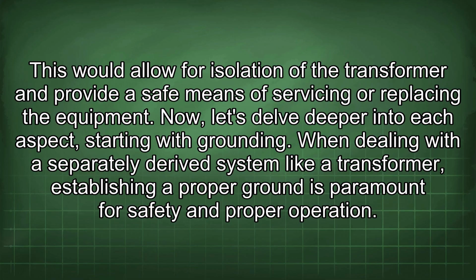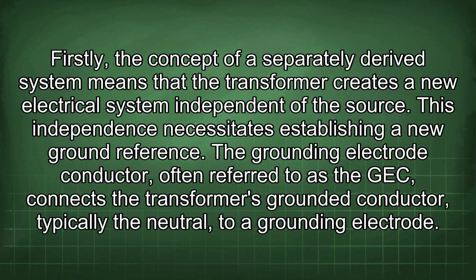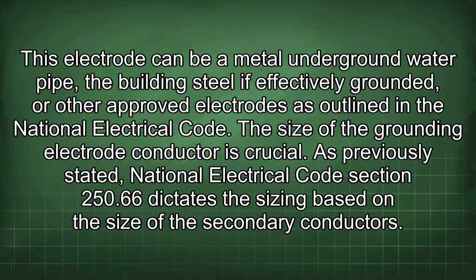Now let's delve deeper into each aspect, starting with grounding. When dealing with a separately derived system like a transformer, establishing a proper ground is paramount for safety and proper operation. Firstly, the concept of a separately derived system means that the transformer creates a new electrical system independent of the source. This independence necessitates establishing a new ground reference. The grounding electrode conductor, often referred to as the GEC, connects the transformer's grounded conductor, typically the neutral, to a grounding electrode. This electrode can be a metal underground water pipe, the building steel if effectively grounded, or other approved electrodes as outlined in the National Electrical Code.